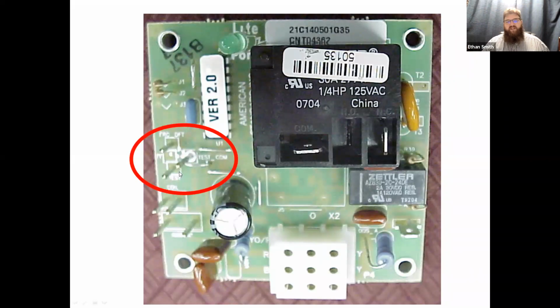The way we test the timers and the terminations, another way is we can use these test pins that are on the defrost boards almost universally now. And so we've got our test common. If we short from test common to force defrost, it will force the unit into defrost.